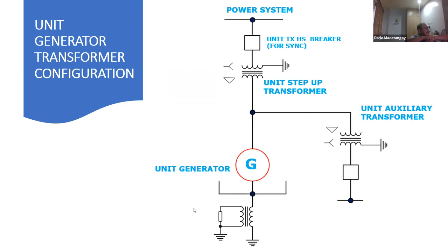Now, we go to the generator plant configuration, typical generator configuration. This one is a unit, the most fundamental configuration. It's a unit generator transformer configuration. When we say it's a unit, it's the whole assembly here, the generator, the unit transformer, and the step up, are all actually turned on and off all together, okay?